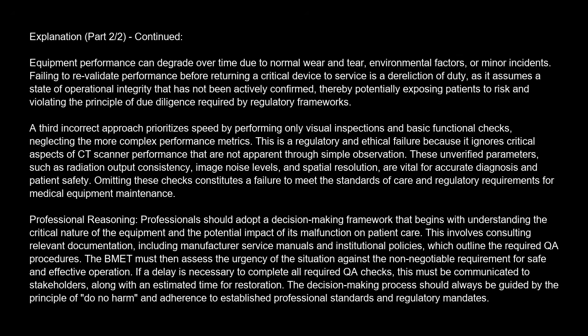Professional reasoning. Professionals should adopt a decision-making framework that begins with understanding the critical nature of the equipment and the potential impact of its malfunction on patient care. This involves consulting relevant documentation, including manufacturer service manuals and institutional policies, which outline the required QA procedures. The BMET must then assess the urgency of the situation against the non-negotiable requirement for safe and effective operation. If a delay is necessary to complete all required QA checks, this must be communicated to stakeholders, along with an estimated time for restoration. The decision-making process should always be guided by the principle of do no harm and adherence to established professional standards and regulatory mandates.